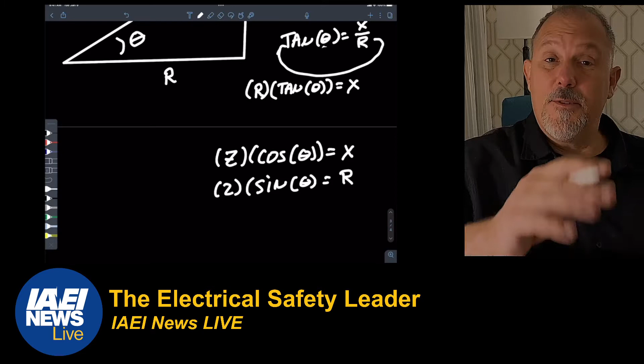Because now I can take this transformer, for example, a 500 kVA transformer with a 4% impedance, and if they gave you an X to R ratio, I can calculate the R and the X.